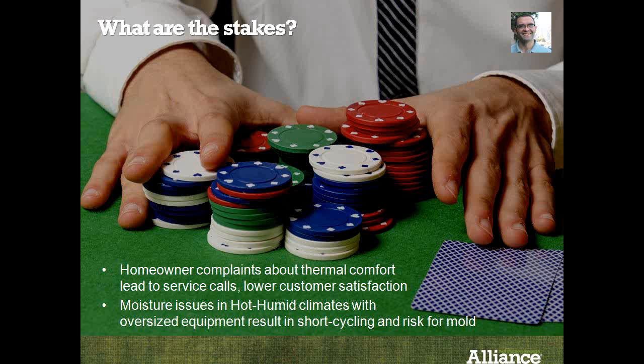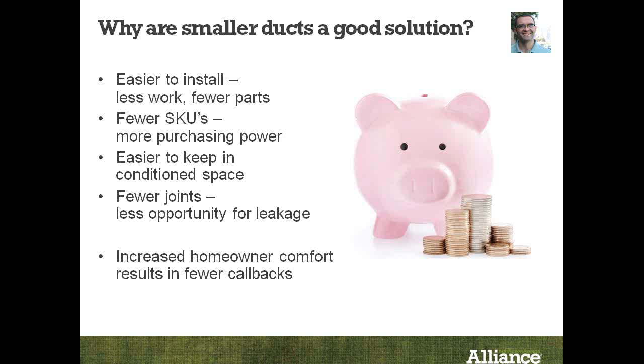So how do you meet the need of the customer even in climates that are hot and humid? Let's say you have a large system in a hot, humid climate like Houston, Texas. If you have short cycling, you aren't going to remove the moisture, and then you're going to have potential for mold growth. So the stakes are pretty high. You could have customer complaints, or you could have potential durability issues, and you really don't want either. So one of our solutions that we've been investigating is small diameter ducts.